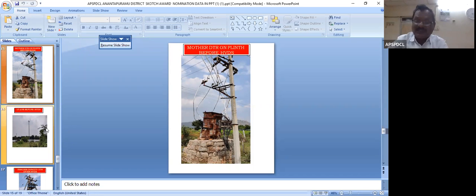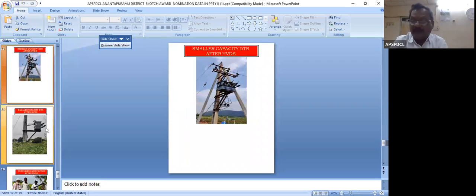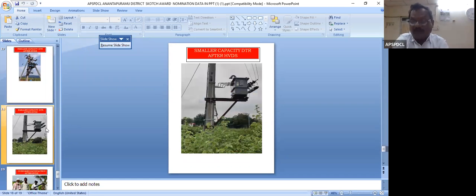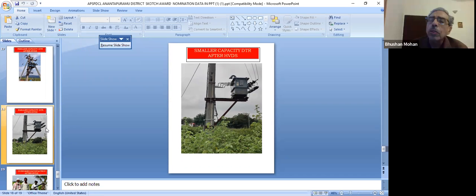Yes, sir. Instead of one place, it directly goes to a 25 KVA transformer erected at the farmer's end only, sir. At bore level, we are erecting a new transformer for 2 to 3 farmers only. 11 kV is given to this transformer, and voltage is 450. Earlier, each transformer was feeding around 20-30 farmers.